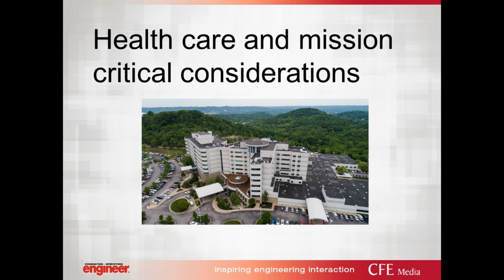The number one thing that we must assess for these facilities is the likelihood that employees or guest employees, which would be contractors, will actually be required to clean, take readings, or interact with energized equipment. Typically, we'll find that this is extremely high because in these facilities, you can't have an entire shutdown just to walk in and clean the room or clean near the equipment.